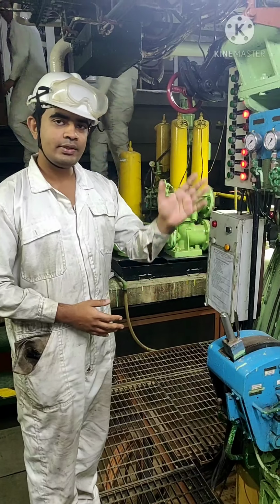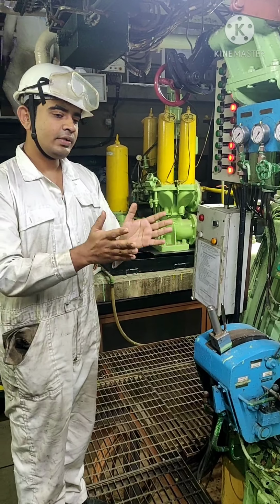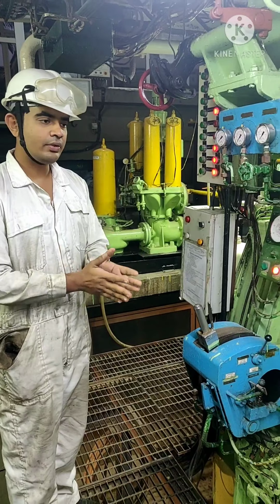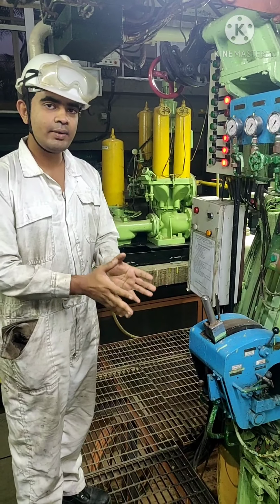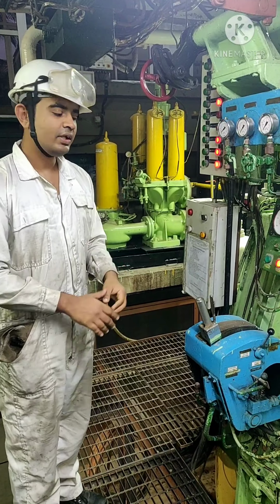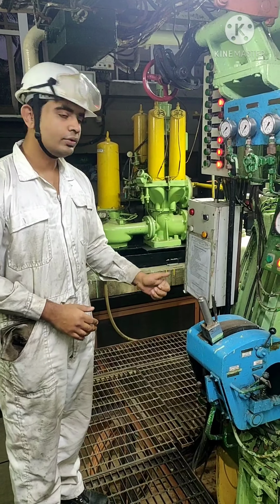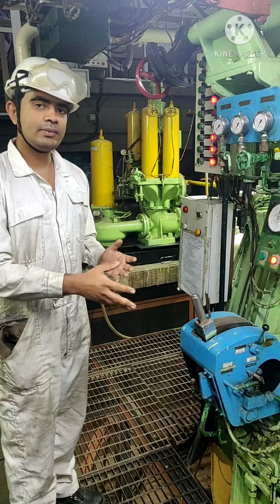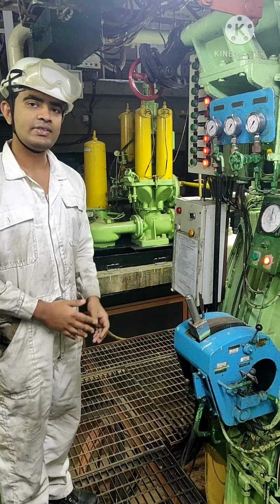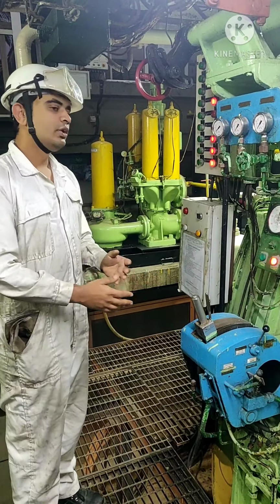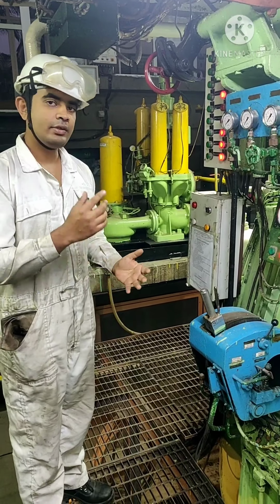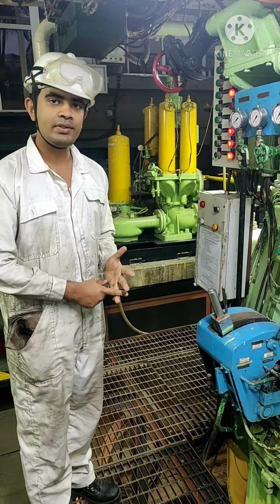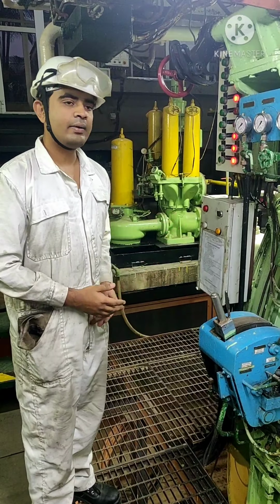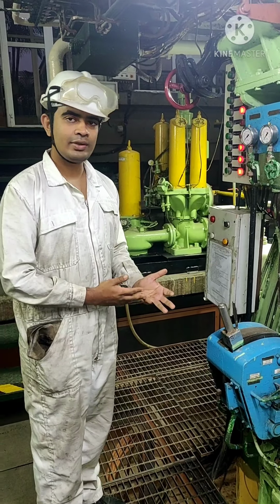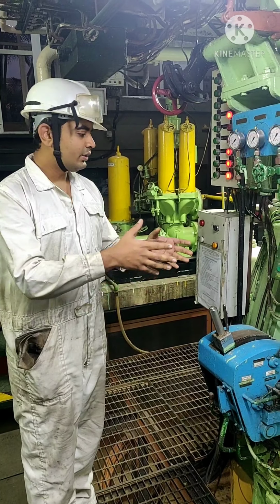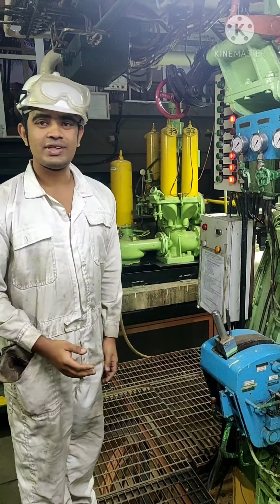Once compressed air is admitted in its firing order, the engine crankshaft is going to rotate and get into its rated RPM, the minimum RPM at which compression is sufficient. Once that is achieved, we change over to fuel. Once fuel is admitted, we can consider the engine as started. We especially check parameters like lube oil pressure, exhaust gas temperature, jacket cooling water temperature, and inlet/outlet temperature and pressure. There we go, our engine is started virtually.